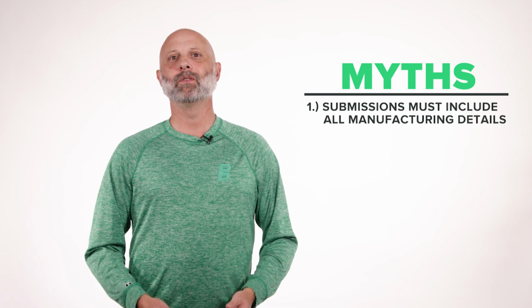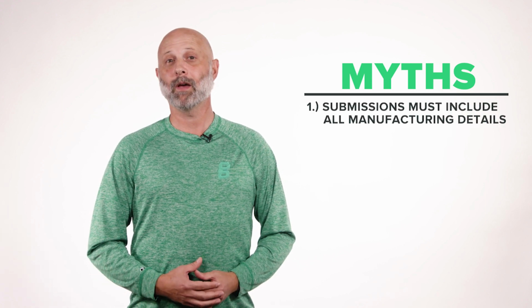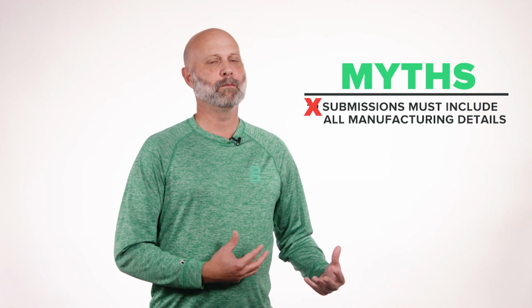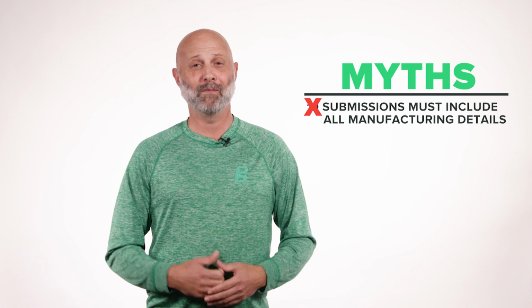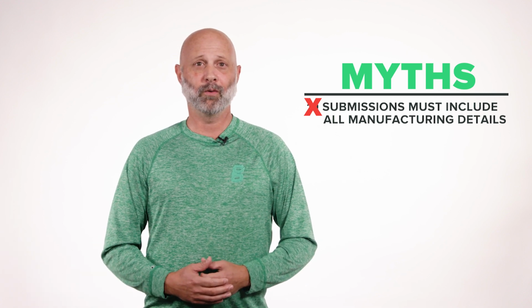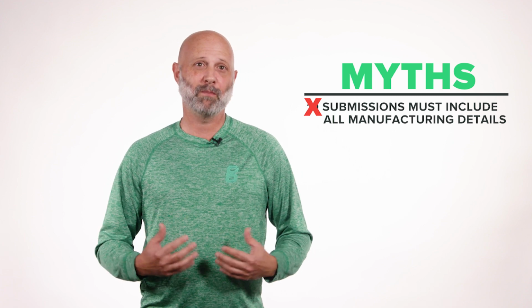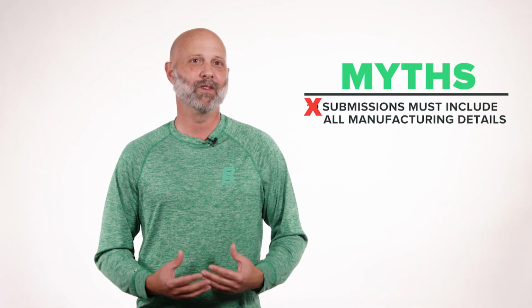Here are some common myths about the approve phase. Myth number one: regulatory submissions must include all details of manufacturing processes. The reality is that's not always the case. In fact, the most common case is that manufacturing information is not included in a regulatory submission. A regulatory submission is primarily design-based and focused, and the goal is to assess the safety and, in some cases, efficacy of a medical device with respect to the stated indications for use. This is demonstrated through sound design controls and risk management.